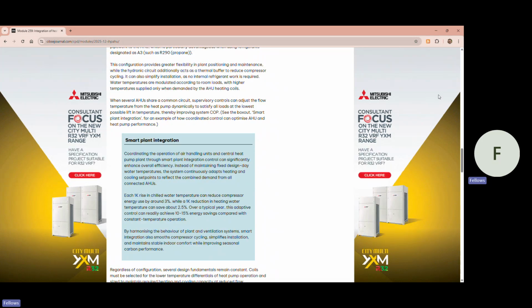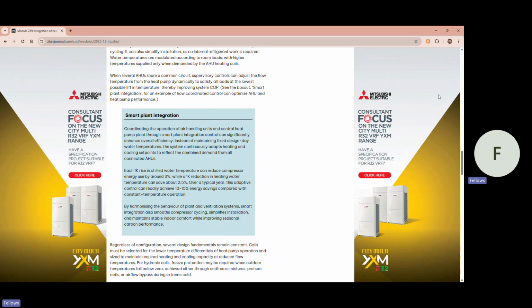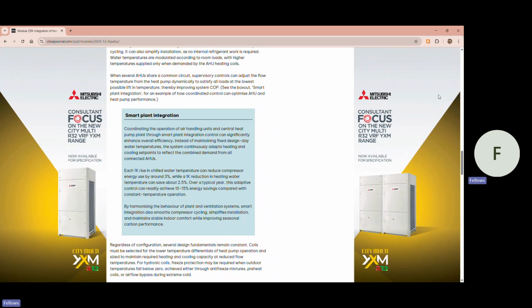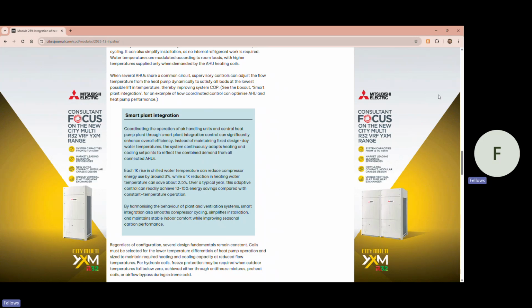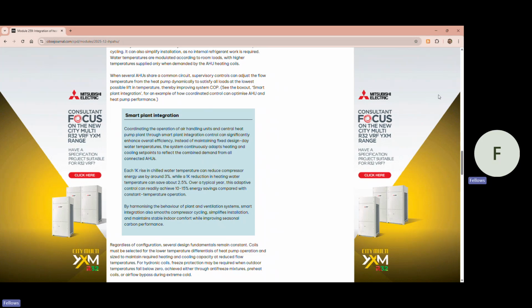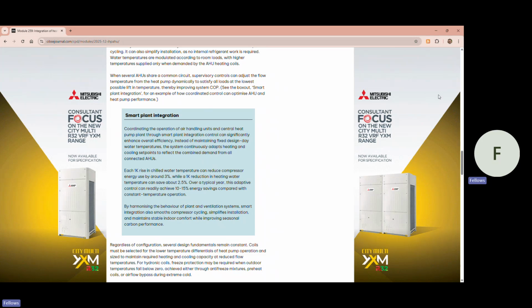Smart plant integration. Coordinating the operation of air handling units and central heat pump plant through smart plant integration control can significantly enhance overall energy efficiency. Instead of maintaining fixed design day water temperatures, the system continuously adapts heating and cooling set points to reflect the combined demand from all connected AHUs.